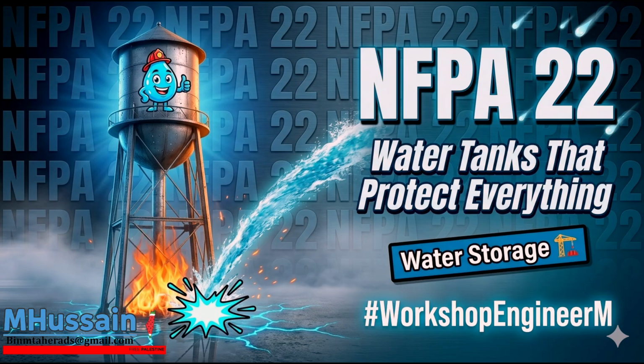It requires regular inspection and maintenance. And the hydrostatic pressure inside that vertical pipe is immense. If the tank is 100 feet in the air, you have roughly 43 psi of static head pressure bearing down on that valve, plus the raw weight of the water column. If a maintenance crew needs to service that valve, they cannot safely unbolt a 500-pound piece of cast iron while suspended on scaffolding 50 feet in the air, especially while fighting the static pressure of a fully loaded pipe. Putting the valve horizontally in a frost-proof pit at our base ensures it can be safely isolated with control valves, completely drained, and serviced by technicians standing safely on the ground.